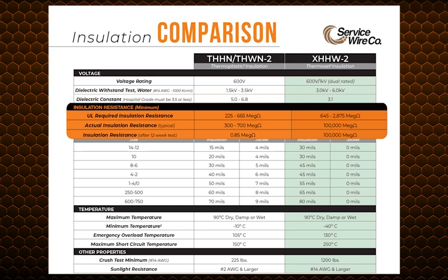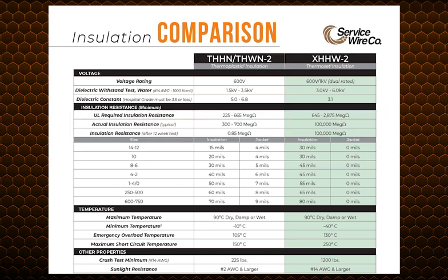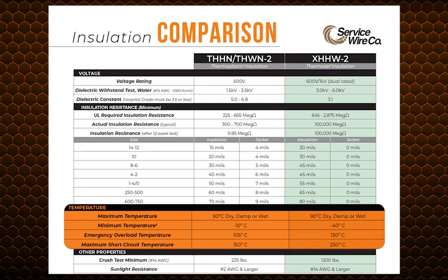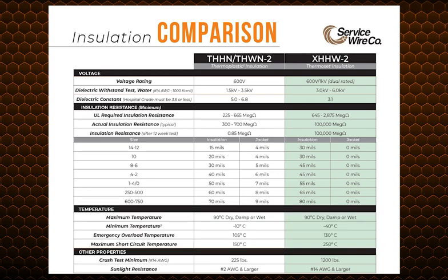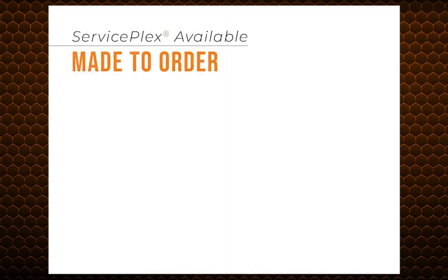This means the XHHW cable can handle more spikes and inrushes over longer periods of time while protecting critical circuits at risk of electrical interference from high leakage currents. XHHW-2 also has a high maximum temperature rating, protecting the cable in open air installations. And finally, the thermoset XLPE compound has almost 5 times the crush resistance of thermoplastic products, proving to be a more durable and reliable cable.